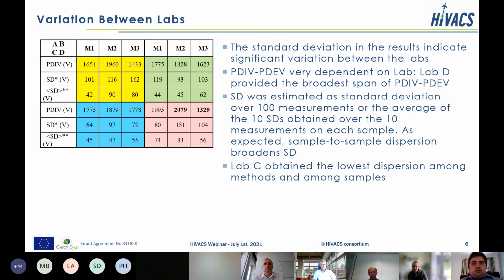These are the standard deviations in the results between each of the labs. The lab with the smallest dispersion is Lab C. Lab D had the largest dispersion of results, including the biggest difference between the PDIV and the PDEV values for each of the labs that participated. And the most likely explanation for this observation is that Lab D performed their measurements in a room that was screened from ambient sources of electrical noise. So the chances are that that lab was able to detect much lower levels of discharge than the other laboratories were.